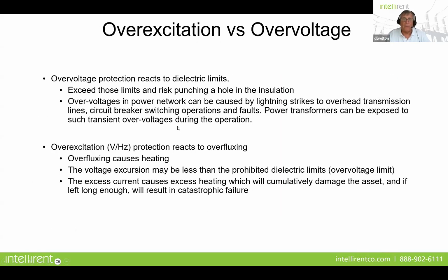Okay, so what causes this? Well, overexcitation is different from overvoltage because overvoltage protection reacts to dielectric limits. And this could be due to lightning strikes on overhead transmission lines, circuit breaker switching operations, anywhere where your voltage is going to spike. That's going to create a problem in the insulating system of the transformer and actually put a hole in the insulation. But overexcitation is different. It's protecting against what we call overfluxing. Okay, tough word to say. Be careful how you say it. But overfluxing basically causes heating in the transformer. And the voltage excursion may be less than the prohibited dielectric limits of an overvoltage limit.